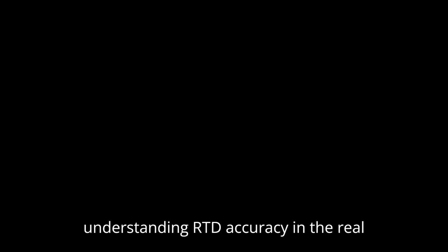Now, RTDs are famous for accuracy, but you hinted that this precision comes with a catch, especially regarding the wiring. Why do we need different wiring setups, like 3-wire and 4-wire? Why does the resistance of the connecting wires matter so much? This is absolutely crucial for understanding RTD accuracy in the real world. The challenge is this. The platinum sensing element itself might be very precise, say 100 ohms at 0 degrees C. Right. But you need to connect that sensor, which is out in the hot or cold process pipe, back to the transmitter or control system, often many meters away, using copper wires. Standard copper wires. Standard copper wires.